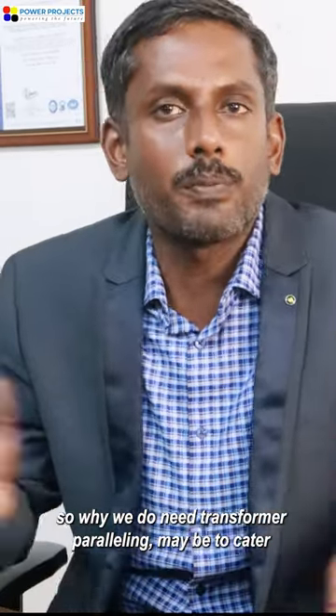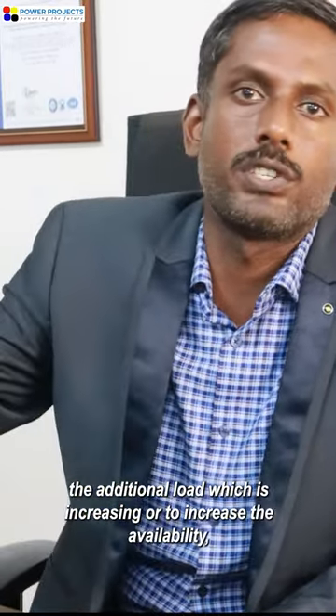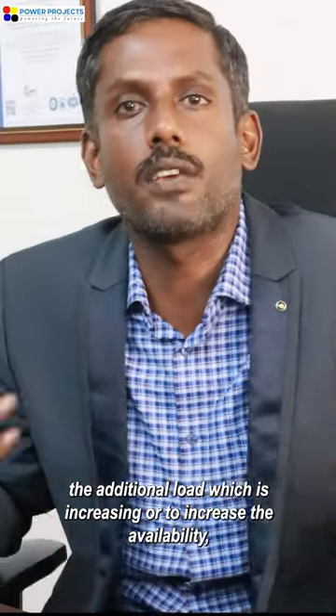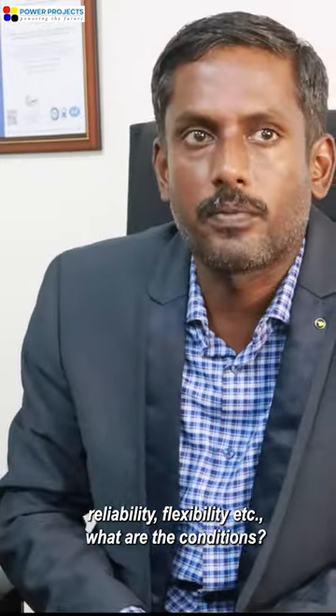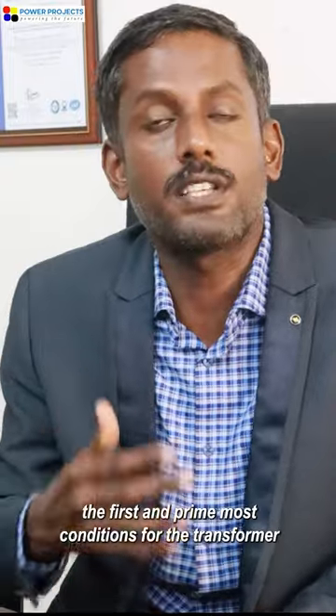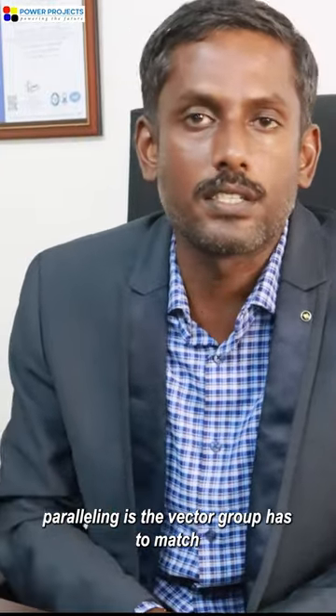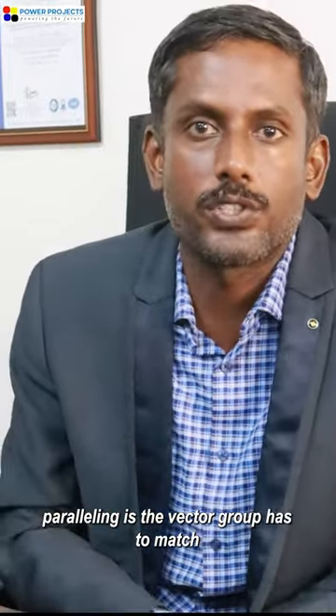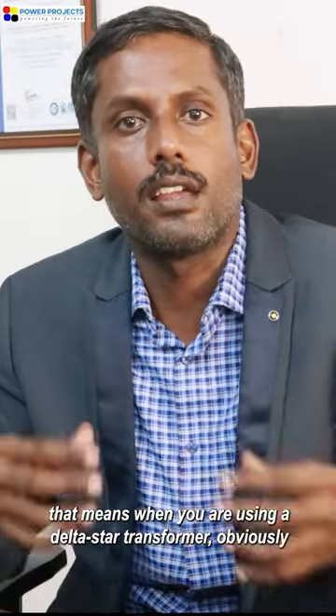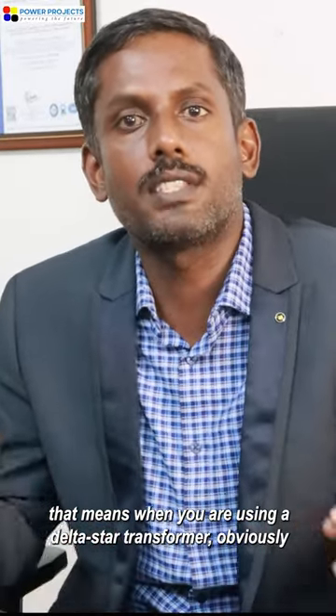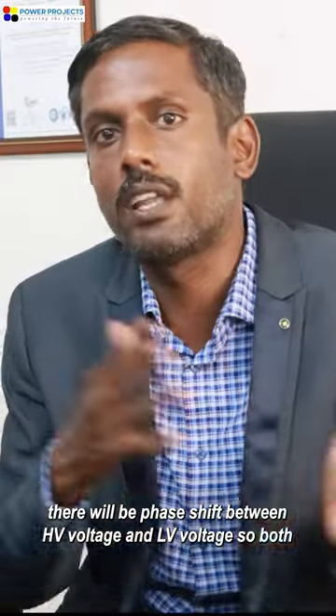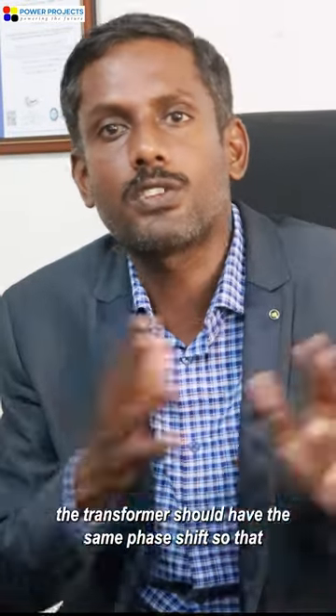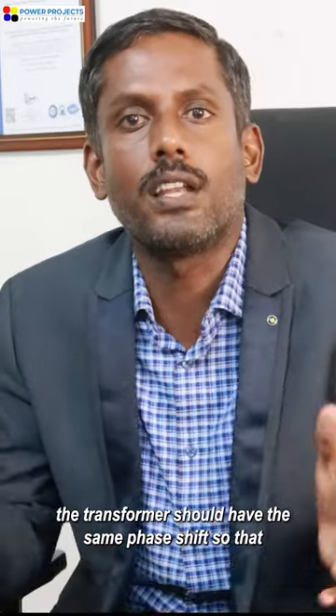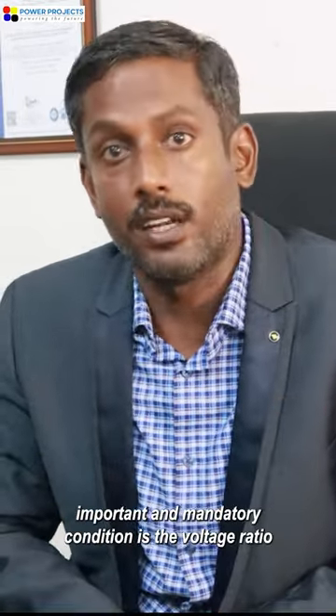So why do we need transformer paralleling? Maybe to cater to the additional load which is increasing, or to increase the availability, reliability, flexibility, etc. What are the conditions? The first and prime condition for transformer paralleling is that the vector group has to match. That means when you are using a delta star transformer, obviously there will be a phase shift between HV voltage and LV voltage. So both the transformers should have the same phase shift so that there will not be any resultant short circuit. The second important and mandatory condition is the voltage ratio.